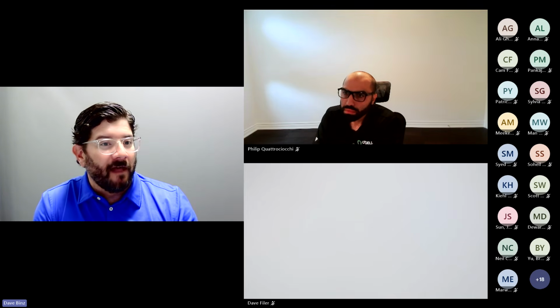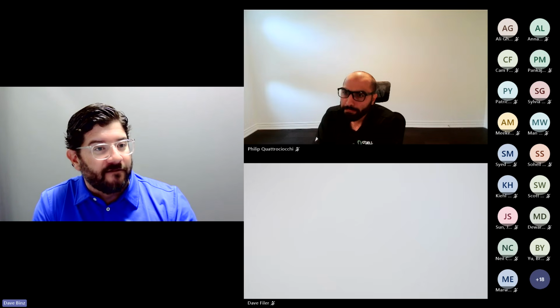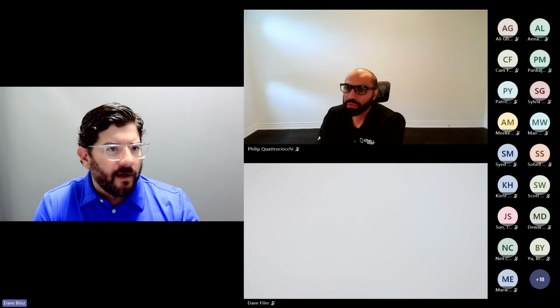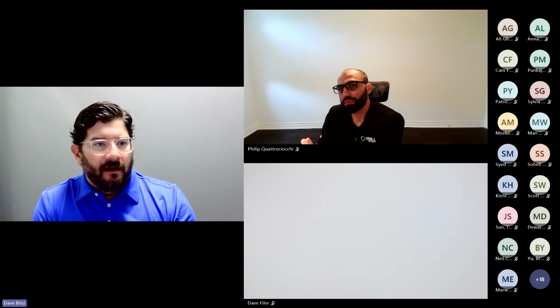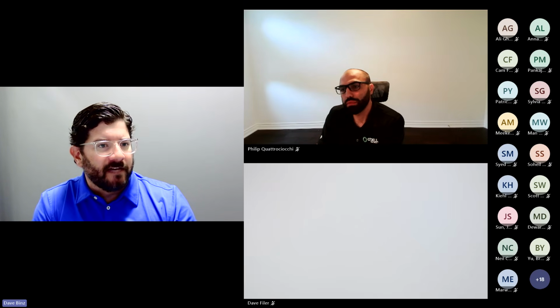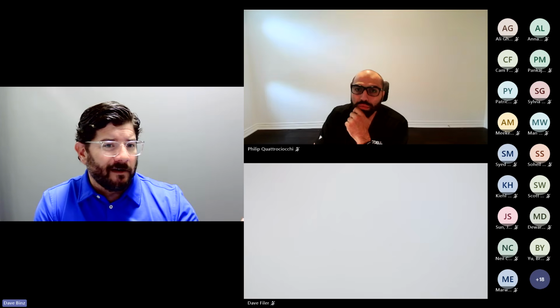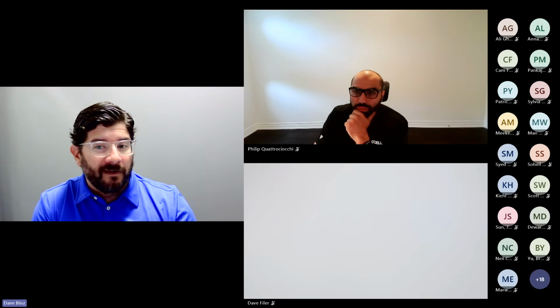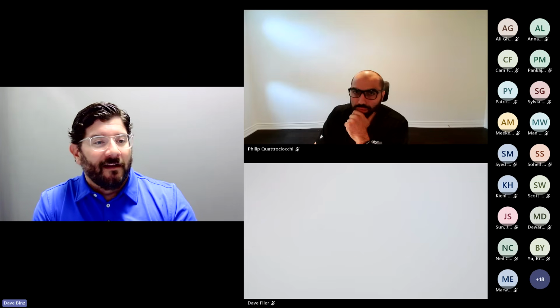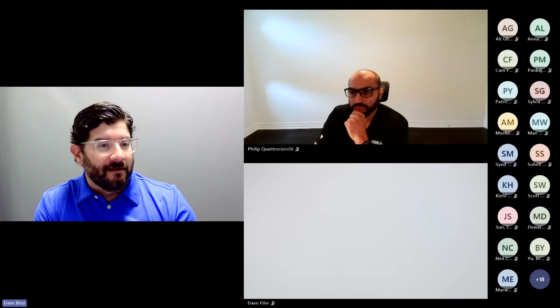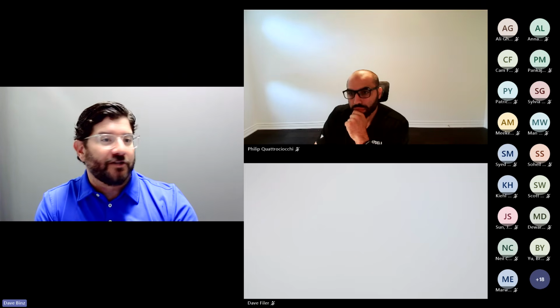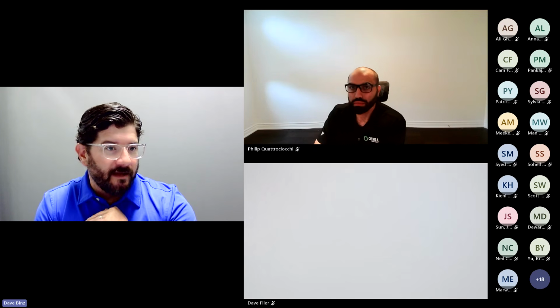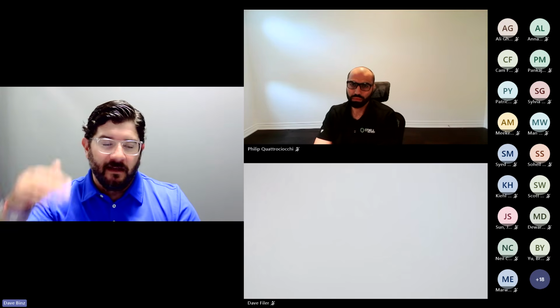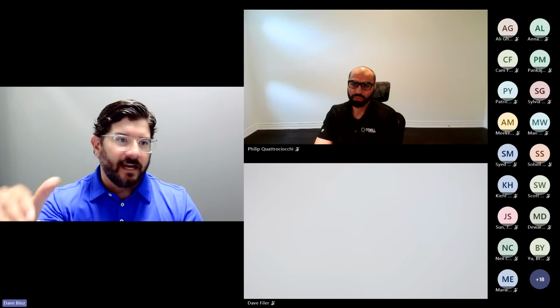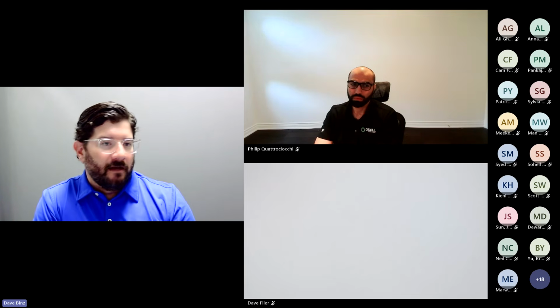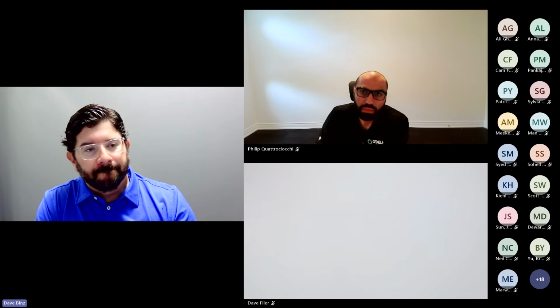So that's where we see a balance, and that's really where indirect evaporative cooling in two-stage, which is a unique way of evaporative technology that most contractors, users, and engineers don't often see every day. It's used a lot in some data center markets, the indirect evaporative cooling, not as much in industrial manufacturing. And so it can be a unique way to provide cooling and ventilation where I'm not trying to completely dehumidify and comfort control the space, but I want to take a 110-degree indoor environment to 90 degrees without adding compressors. It becomes a very attractive solution.